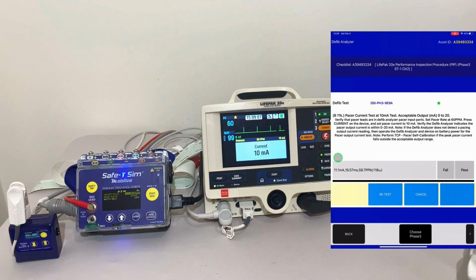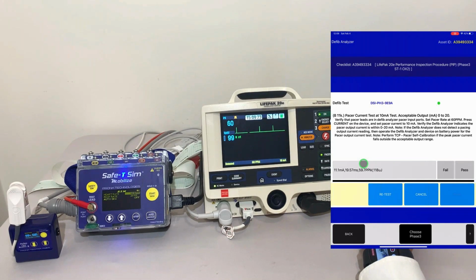You can see here the measured current on a target of 10 milliamps is 11.1. We have 19.7 milliseconds, and the pulses per minute that we have programmed is 60, and we measured 59.7, and a 118 microjoules measurement. So we want to make sure that we're within range. We need to make sure we're within 0 to 20 milliamps, and we clearly here are real close to the target at 11.1. So we've passed this test.